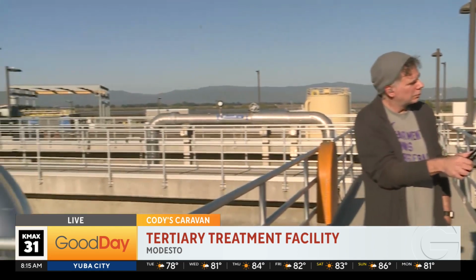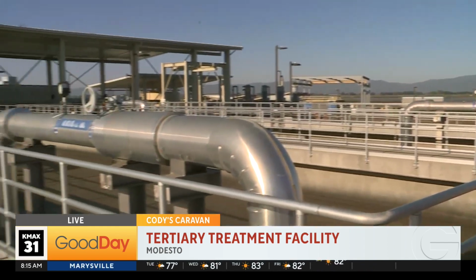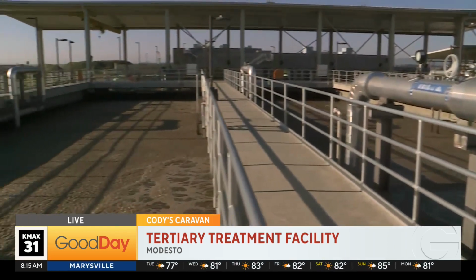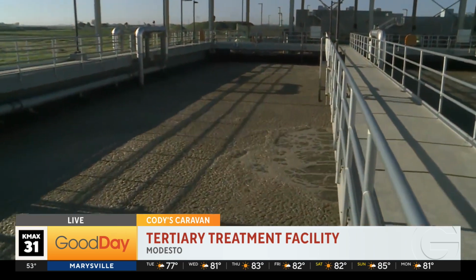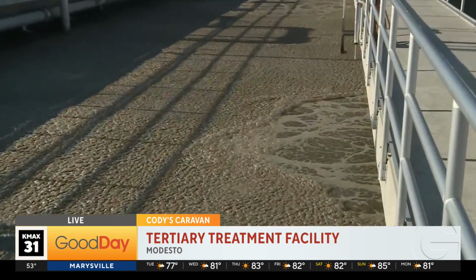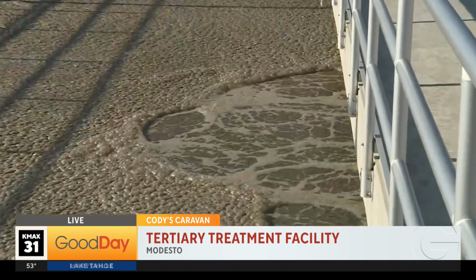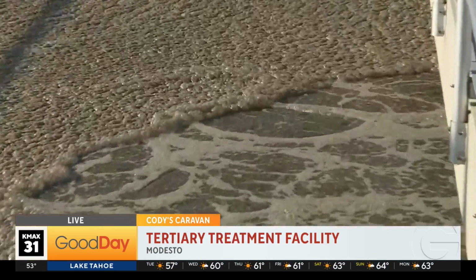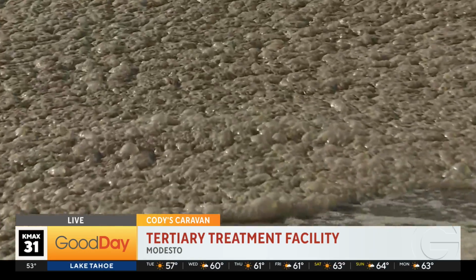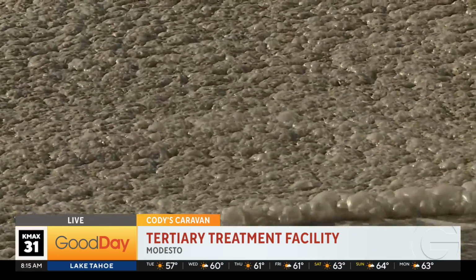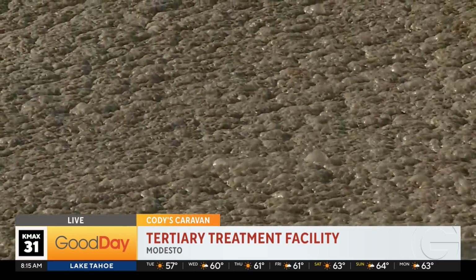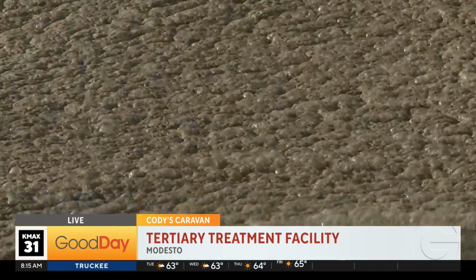Okay, so we're in step 2. What is this going on here? Yeah, so this is the biological treatment process. What we're doing here is we're taking the wastewater, we're infusing it with oxygen, recycling it enough so that it gets enough passes through the oxygenation system so that we can provide a source of oxygen for the microbes and the bacteria to respirate and use that to consume the waste that's in the water.